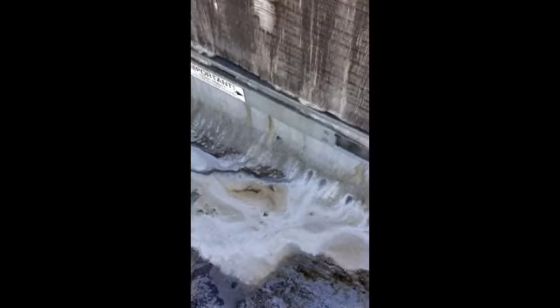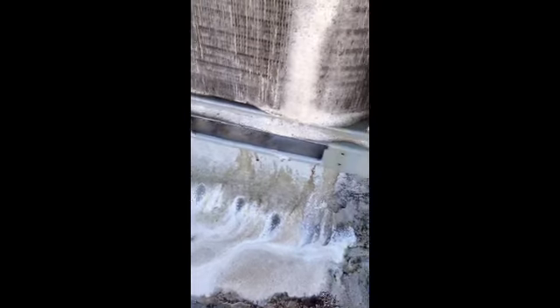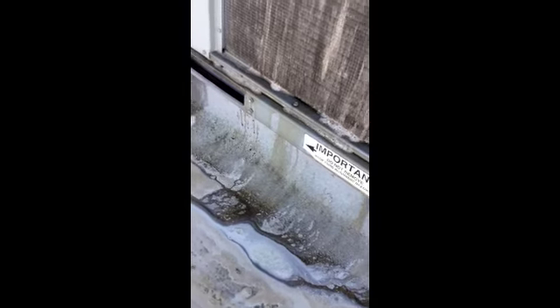I put the foam cleaner on there. You can tell just by looking at the grease and the grime coming out of this coil — it's just absolutely grody. It definitely affects the system operation. This coil gets clogged up with grease, your dirt starts sticking, everything starts clogging up, and it's going to affect the efficiency of your system.